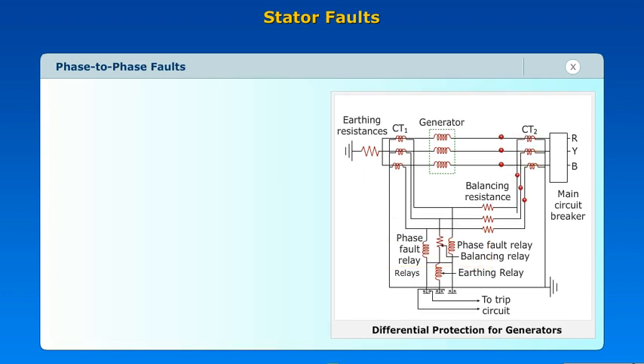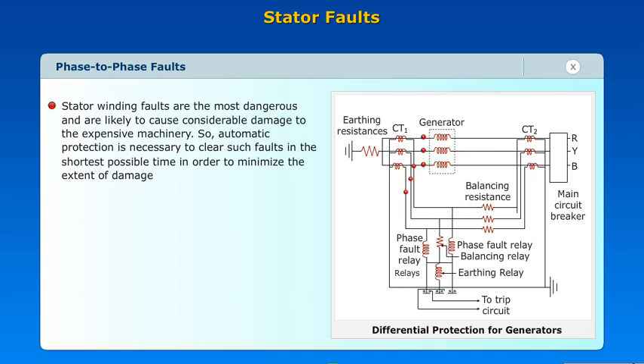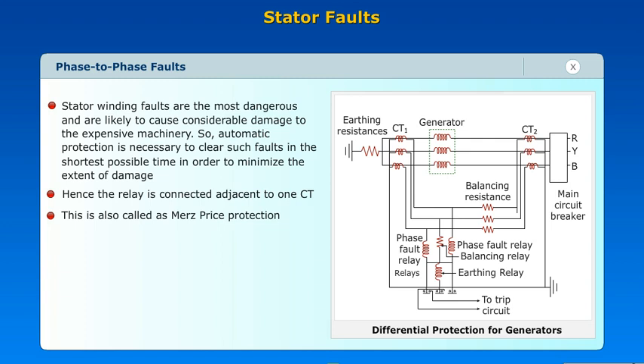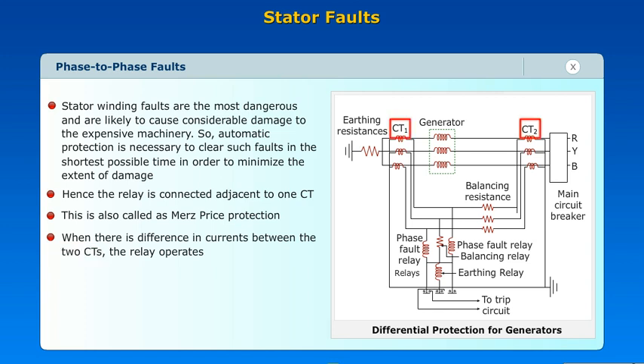Phase-to-phase faults: stator winding faults are the most dangerous and are likely to cause considerable damage to the expensive machinery. So automatic protection is necessary to clear such faults in the shortest possible time in order to minimize the extent of damage. Hence, the relay is connected adjacent to one CT. This is also called Merz Price protection. When there is a difference in currents between the two CTs, the relay operates.